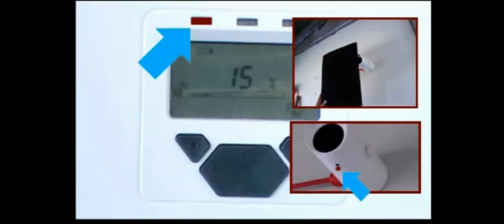To perform a manual alarm test, slowly cover half the receiver using non-reflective material, taking more than 2 seconds to do so. After the delay to alarm time, the system controller indication LED and relay pair corresponding to this receiver will now be in an alarm condition. Uncover the receiver to return the system to normal operation. Commissioning is now complete.